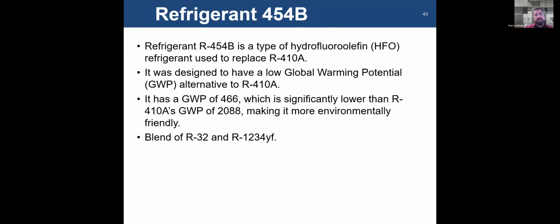Quick note on refrigerant 454B. So 410A was the old refrigerant, 454B is the new refrigerant. As of January 1st, 2025, all systems that you purchase will come with 454B. It's the new replacement for 410A. They're not interchangeable, just so you guys know. Why 454B? It has a global warming potential much less than that of 410A. All right. So remember, anybody that's been around for a while, R22 was the old refrigerant that was used for years. It had a higher global warming potential than even 410A.